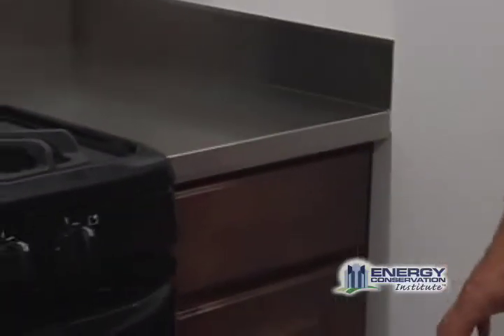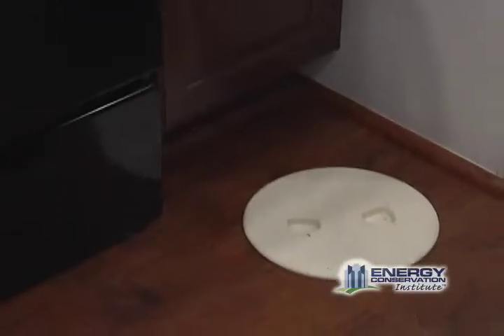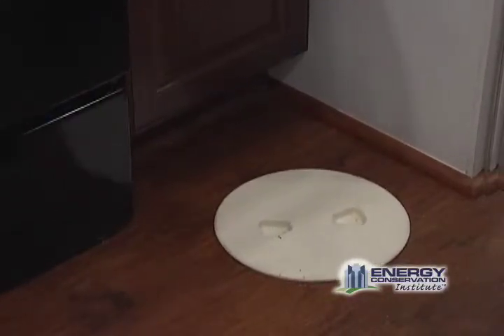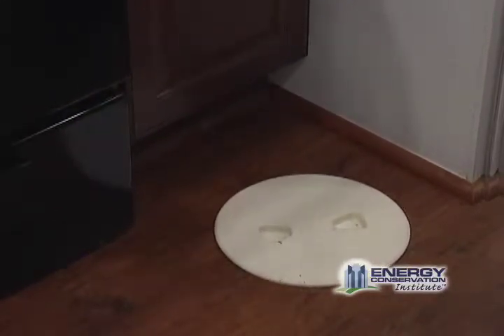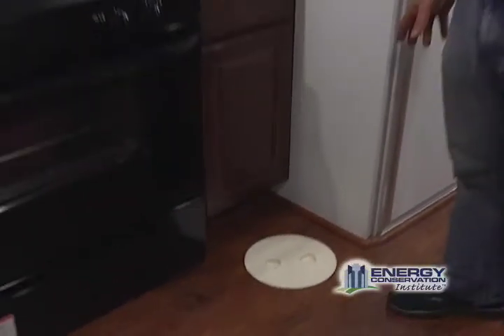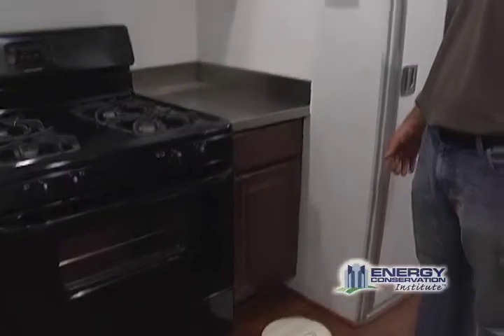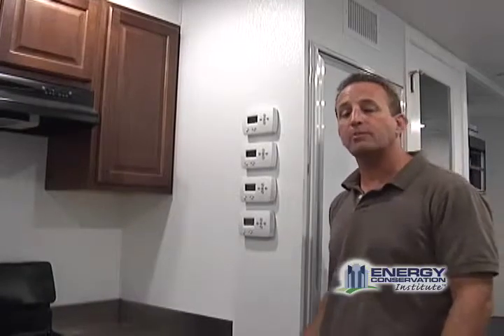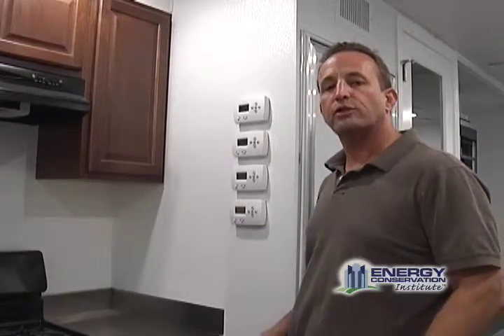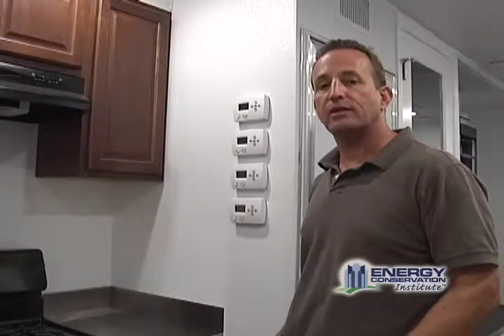Down below the thermostats, you'll find another one of those leakage ports that goes to the outside. As a point of reference, there's a total of about 12 leakage ports in either the floor or ceiling throughout the lab. Use these ports to adjust how much leakage you have in the main body or each individual room. These are great when doing blower door testing because you can remove one or two different ports and show how that affects the amount of air leakage throughout the entire lab.